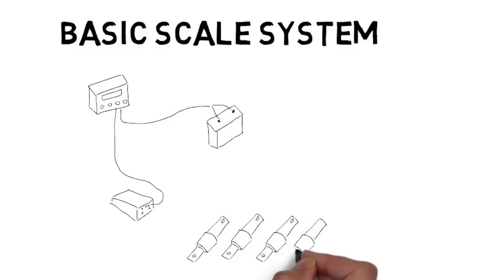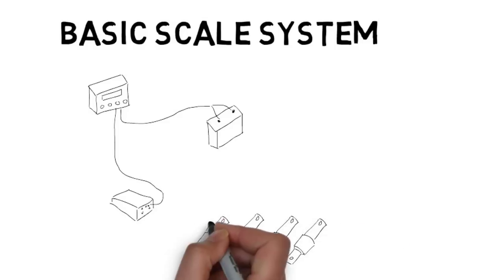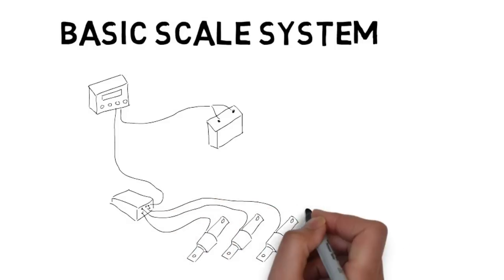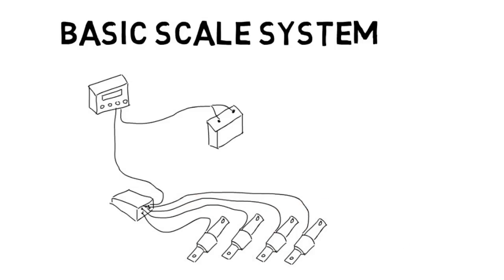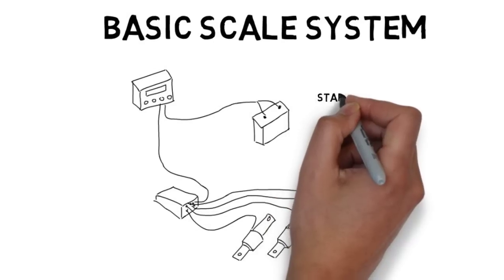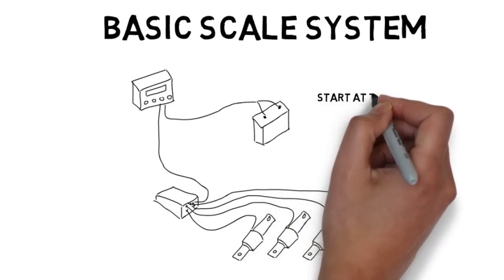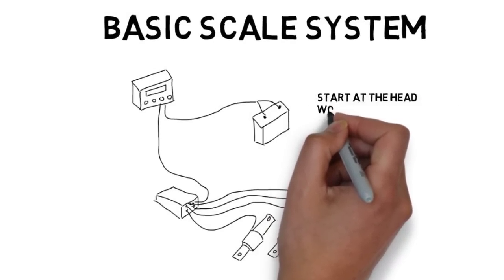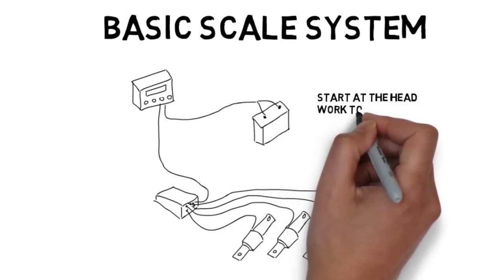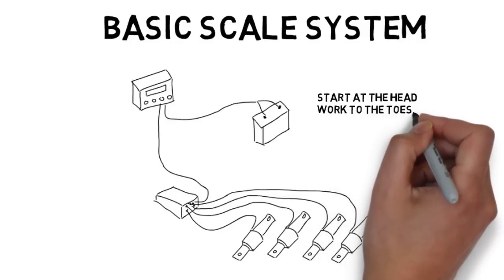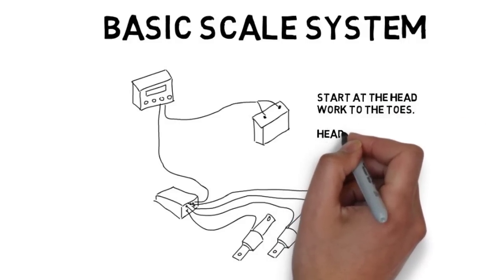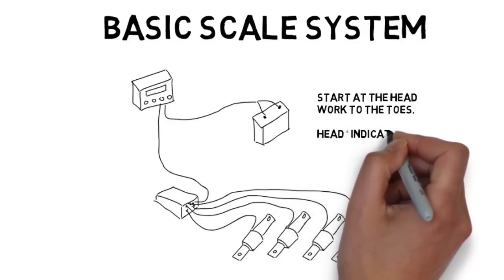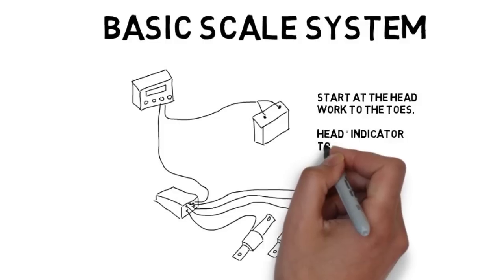The principles of troubleshooting are pretty much the same. When troubleshooting a scale system, you can think of it as starting at the head and working to your toes. The head being your indicator box and the toes being your load cells, with everything else, meaning your junction box, wiring, power source, all in between.